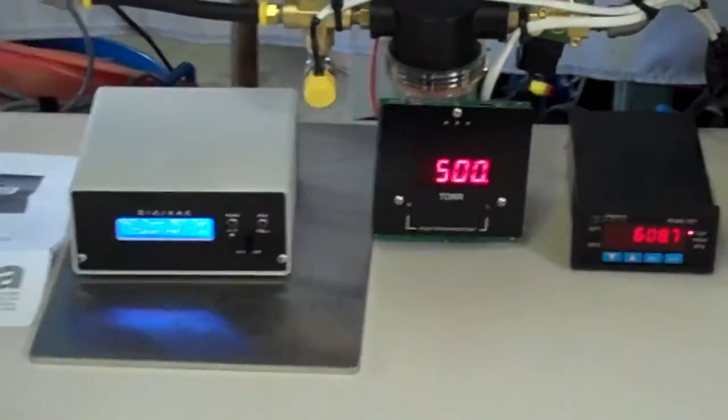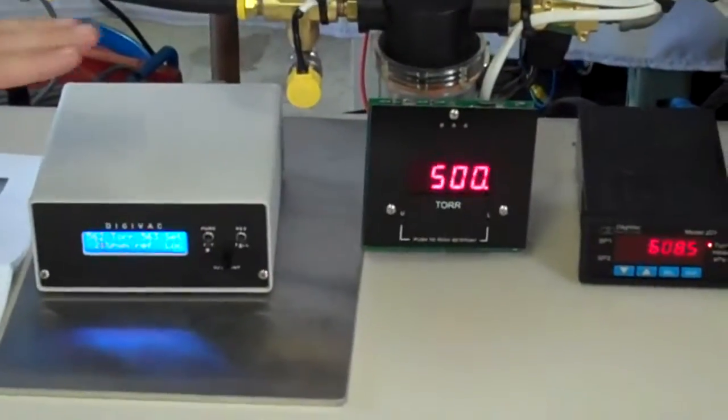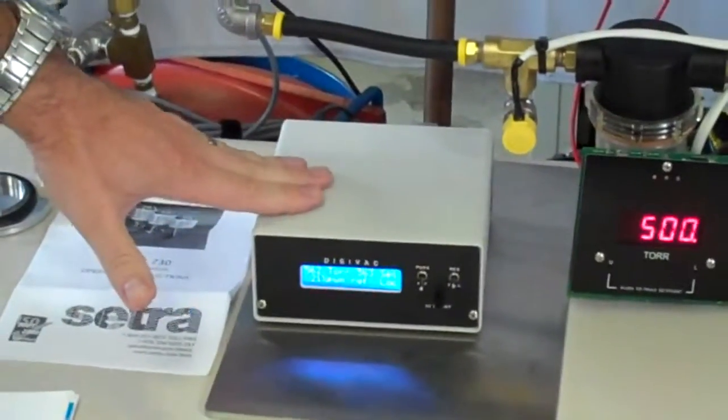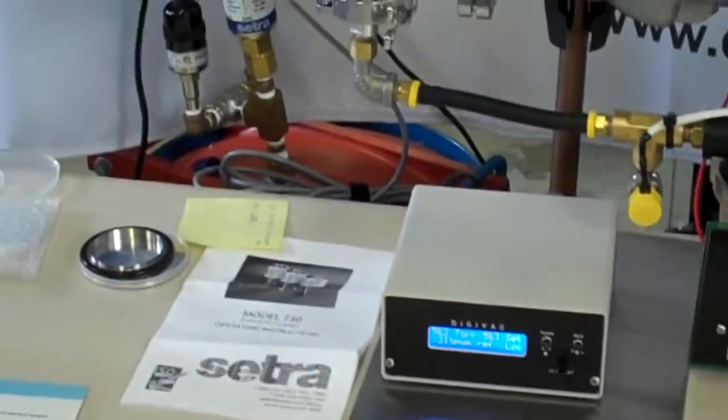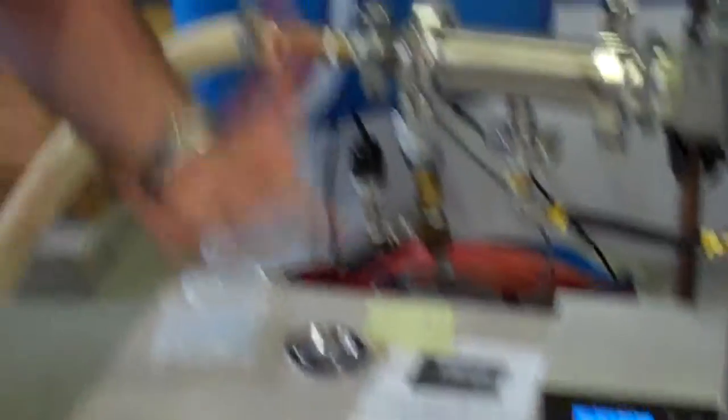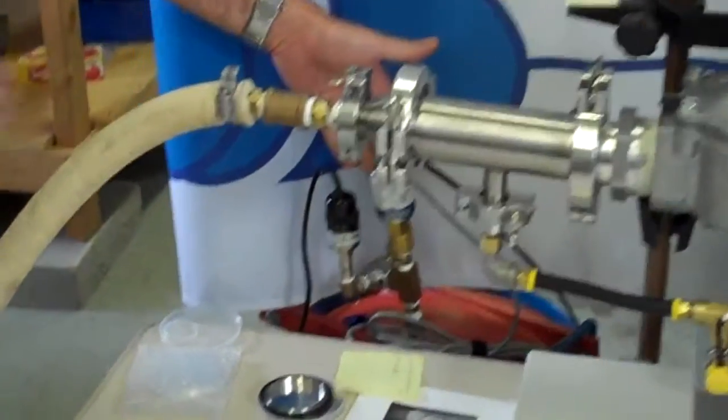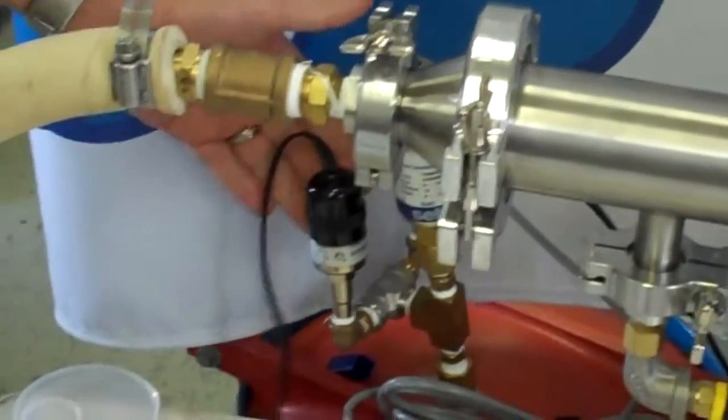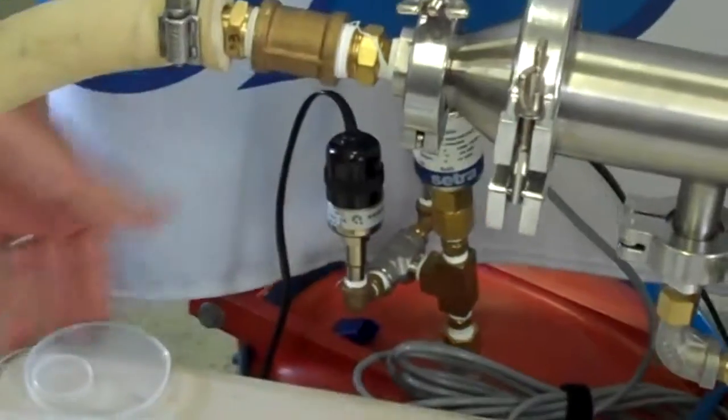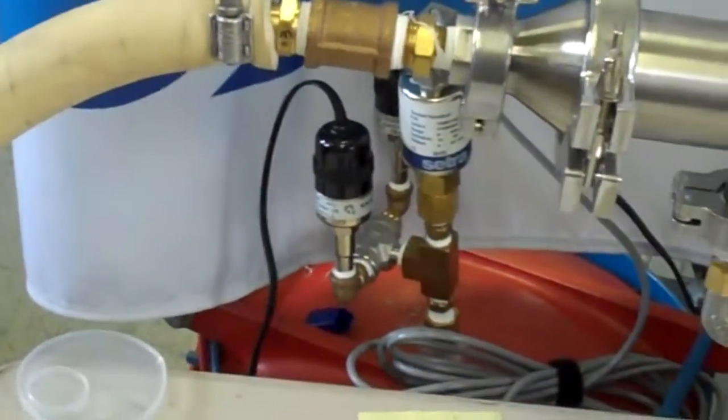How the whole system works is, first we're at atmospheric pressure. They had another requirement where they wanted even better measurement accuracy, so we used a capacitance manometer. Here we see a capacitance manometer actually plumbed into this very technical vessel I have, that's our mock-up control vessel, and also two Baratron 531 vacuum tubes to give us additional vacuum measurement readings that have accuracy in the millitorr range.